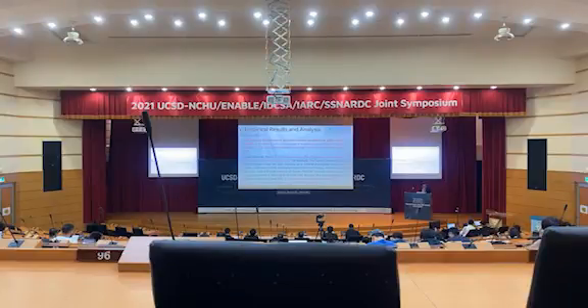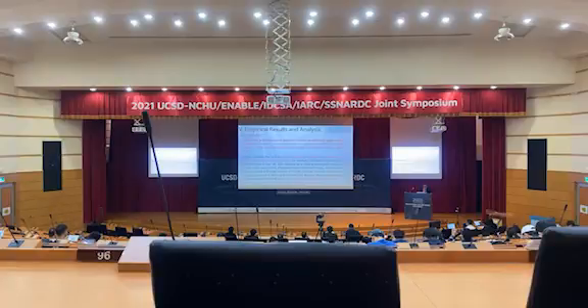Because the regular contracted capacity is 76 kilowatt. Almost every month, it shows that last year in September, also June, October here, we have all been fined by Taipower because we exceeded the contracted capacity. So it is pretty reasonable for us to infer that the regular contracted capacity currently set by the farm was too low. We should adjust the capacity contract with the Taipower so that we can avoid those fines, those penalties.